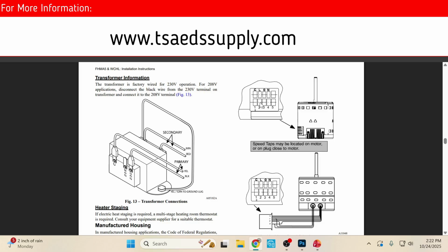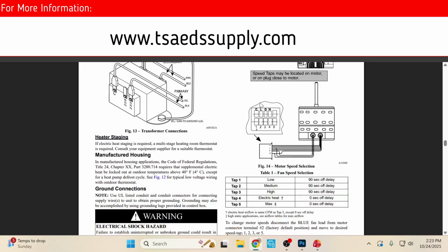So the factory just tests these motors from the factory to see what kind of CFMs they blow to make sure everything's right, and they just leave it in speed tap 2. It's up to the installer to confirm you have, in this situation, 600 CFM, all while blowing 0.50 static pressure or less, delivering that 600 CFM. So that's the responsibility of the installer. Now, why on this particular unit is that important? Because of the leak sensor that you have to go through.